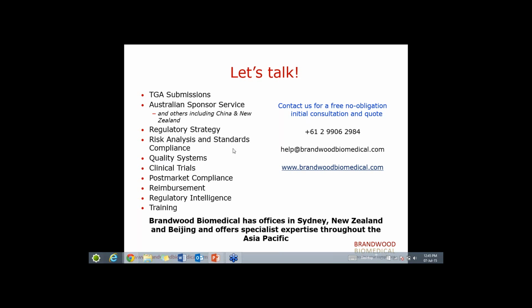There's a question on what international regulatory certifications Australian companies recognize. As I mentioned, it's pretty much Europe. So CE certification. They don't recognize FDA approvals, but it's one of the key differences with New Zealand. Basically, no other jurisdictions apart from Europe. For some IVDs, they may accept Canadian licenses, but again, it's a complex area, and it's usually a case-by-case basis. But the simple answer for that is European certification.